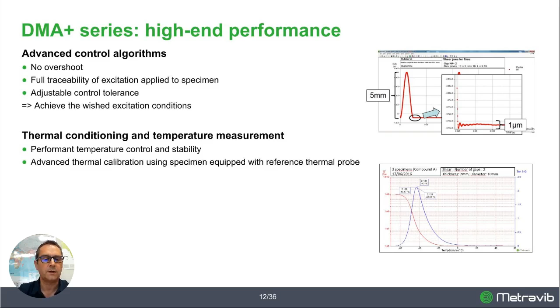The thermal conditioning, of course, is also critical, so we developed a very performant temperature chamber and advanced temperature calibration that make it possible to ensure that the temperature measured corresponds to the temperature seen by the material. This is not so obvious, depending on the size of the specimen, which can sometimes be big. It's important to have specific calibration for those specimens to ensure that the temperature inside the specimen is really controlled and known.